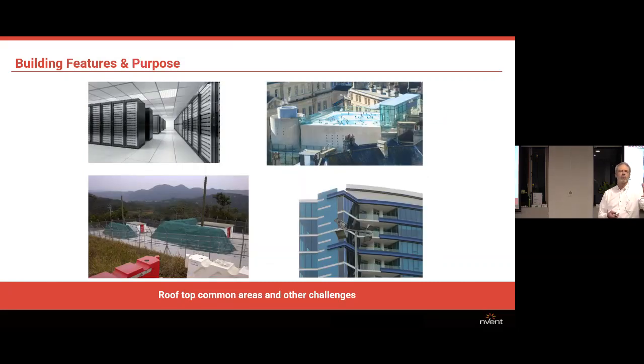Other challenges: lots of sensitive electronics in your building. On the top right, there's a swimming pool, so you can't put lightning rods in the middle of that, so you can't be compliant with the lightning protection standard in that sort of situation. On the bottom left is a simple but complex type of structure, which could be better protected with an active system, which we'll go into soon. And on the right there is a glass covered building where the architects won't want down conductors running down over those glass panels. Excuse me.